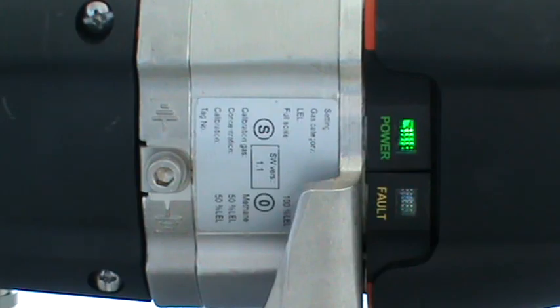And, when being sufficiently stable, the instrument software is comparing the actual measurement reading with the last saved calibration result, to provide later a result about the 0-point drift within that last calibration interval. And this checking of the stability period takes typically 40 seconds, which is 4 times 10 seconds in a row, where defined stability criteria need to be met.